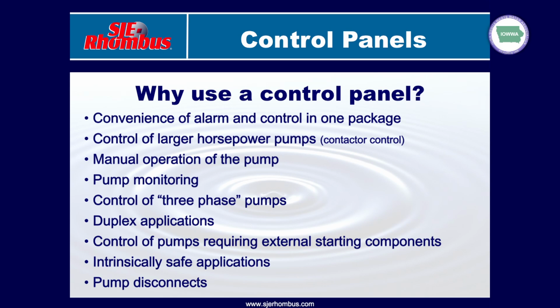Larger horsepower pumps, we know with the switches we're going to be limited to about 15 full load amps on what we can operate with a float switch. With a control panel, the sky's the limit. We're going to size the motor contactor to handle whatever full load amp rating we need for the pump. So we're not limited to a 15 full load amp upper limit for what we can operate. So for larger horsepower pumps, it's going to be mandatory that we go to a control panel.